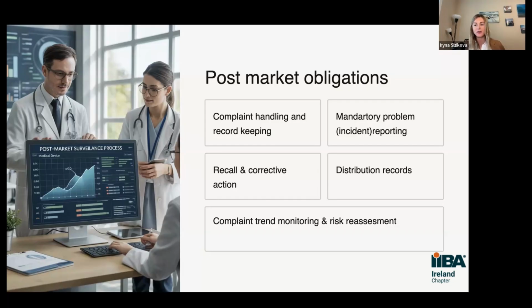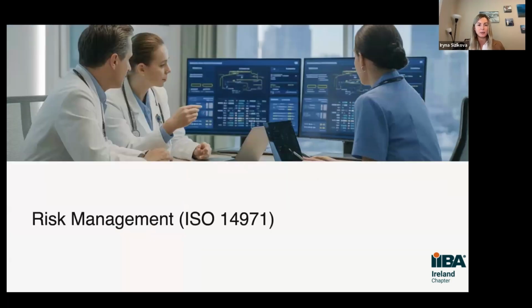We do risk reassessment and re-evaluation. Basically, we monitor how the product behaves on the market after the release, and trends: more complaints, fewer complaints, and whether there are recalls in place. We have to report to the notified body if something serious happens, and if any harm or even death happens to a patient as a result of a software misbehavior. So it's quite serious, and there is a whole team working on this post-market surveillance process.